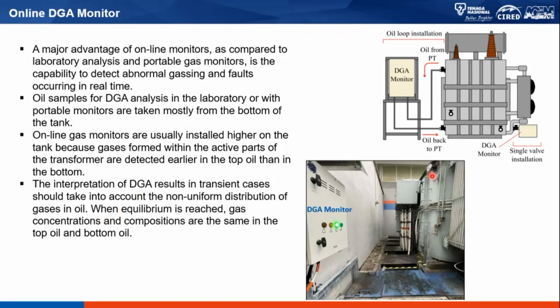The main factor is that when it is in equilibrium, it doesn't matter. So when equilibrium is reached, gas concentration and composition are the same, whether you're taking from the top or from the bottom. To get into equilibrium, normally the transformer is energized for a long period of time, whereby the load is also more stable, and the temperature is also more stable, so that it creates equilibrium within the transformer.